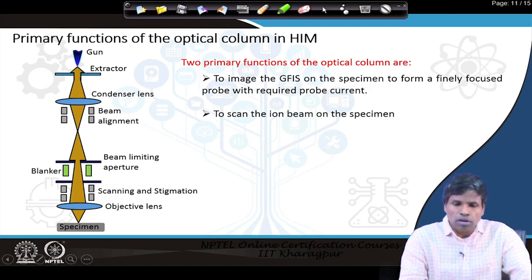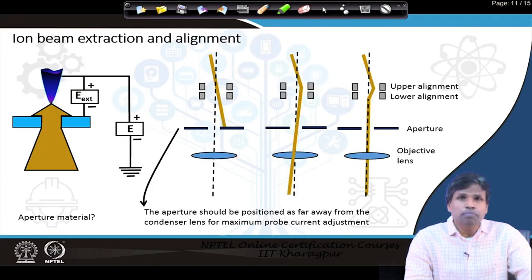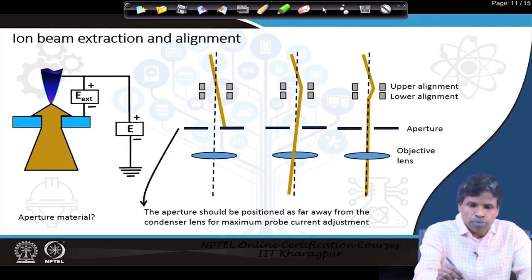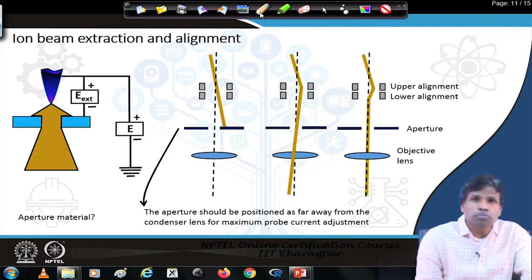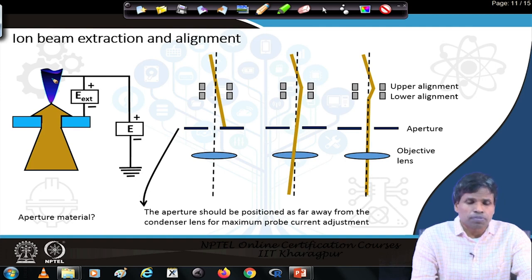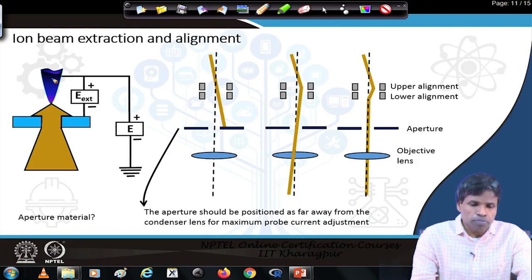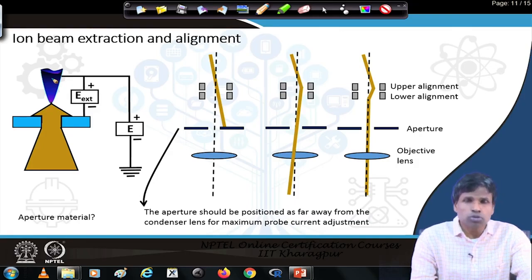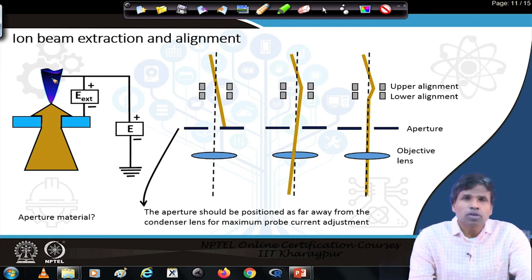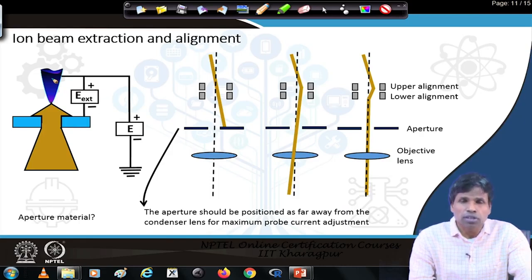The function of the helium ion microscope optical column is to make a fine spot of ions on the specimen and also to scan the ion beam across the specimen. At the top we have the source — the ion gun — and then below that we first have an extractor. The extractor is given a negative potential because the tip is at positive potential, and the extractor will extract the ions from the apex of the ion source by pulling those ions downwards.